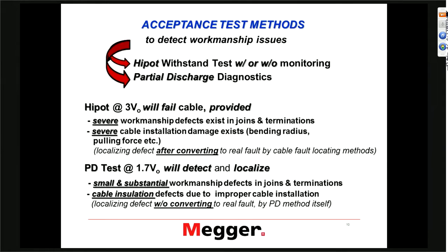Some people might say PD testing can only detect certain defects — and that's correct, because you need basically a high-resistance defect to get a discharge that can be picked up as a partial discharge. But for the most part, workmanship issues in splices and terminations are this type of problem, because you're assembling different type materials on top of each other, and whenever you have very small gaps between them, that's where you have PD building up.